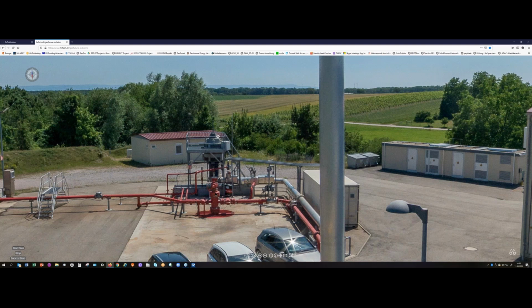Okay. How long is the lifetime of such a line shaft pump? Why are you going to change it? Well, in our particular case, there's a design failure in our line shaft pump at the connecting box, which divides the 39-stage pump into 2 sections. It has been designed with black steel within a stainless steel section, and we fear induced corrosion through the connection between black steel and stainless steel. Therefore, as a preventive maintenance measure, we will deinstall our current pump and replace it with an upgraded pump where this design failure has been eliminated.